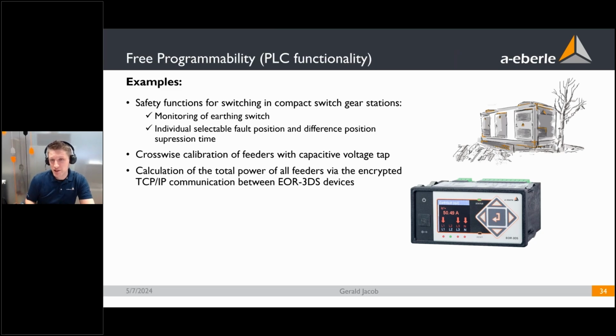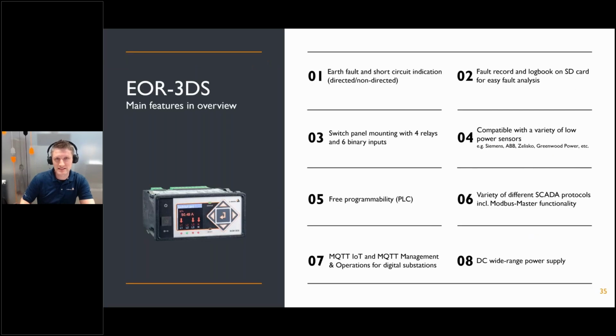PLC functionality I mentioned on the first page. So for switching, for example, customer-specific requirements, we can use a free programmability in the device. Other examples would be crosswise calibration of feeders. So if you have single devices that measure the voltage not very accurately, then you could cross calibrate it via Ethernet if required. Or for example, as mentioned with the Modbus master functionality, a calculation of the total power or any other requirement could be implemented here.